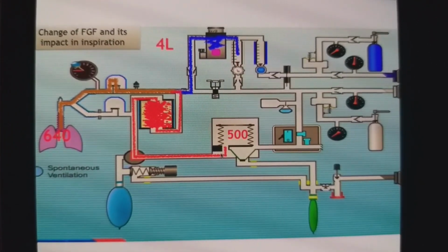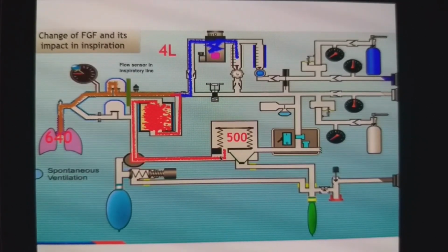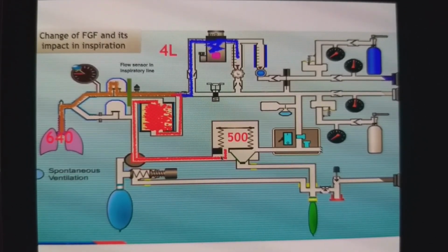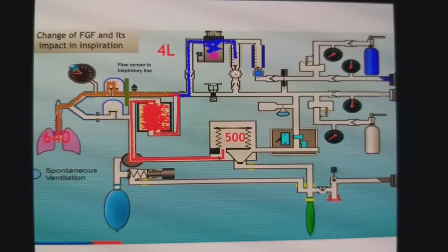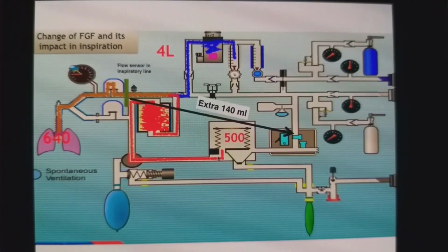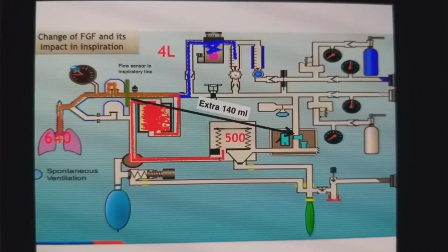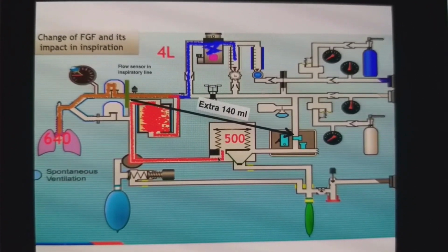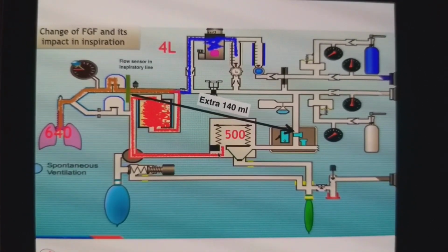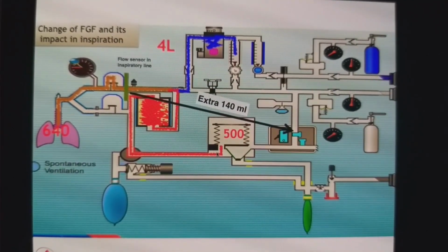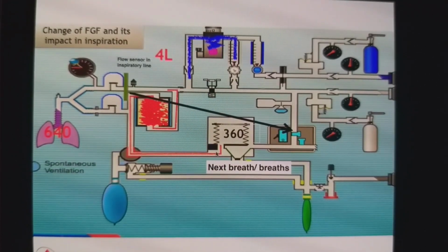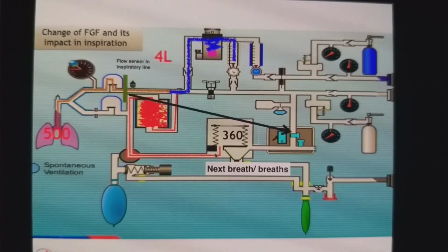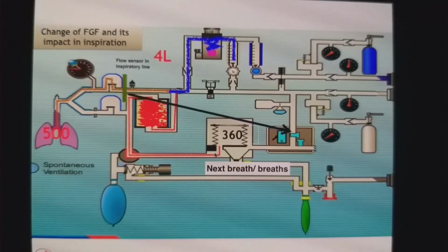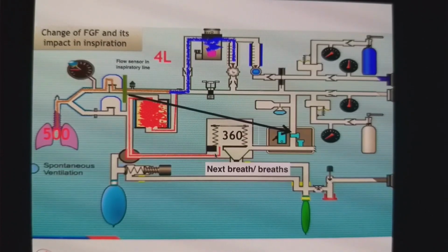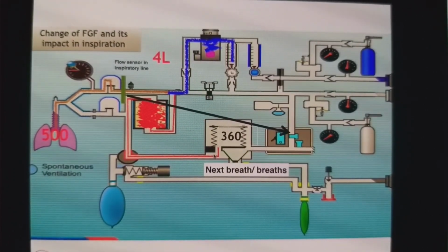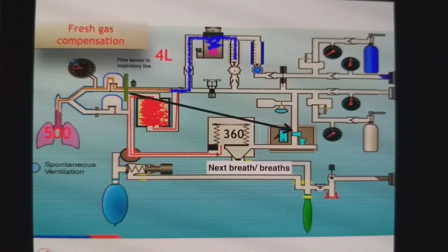Now what other companies have done is add a flow sensor in that inspiratory line to identify the amount of flow. On that machine also, we have set 500 and 640 has been delivered. So the machine knows an extra 140 was given. In the next breath or next few breaths, the bellows will deliver slightly less, only 360 ml. So the end result would be 500, but the bellows are pushing less while more flow is coming in. As soon as you change the flow, in the next few breaths things will change. This is called fresh gas compensation.